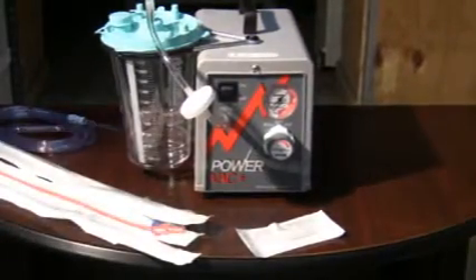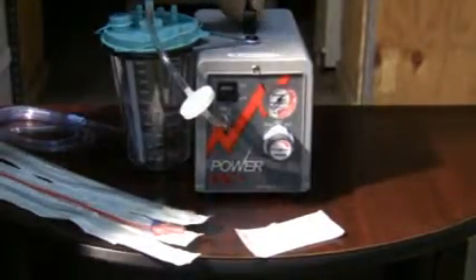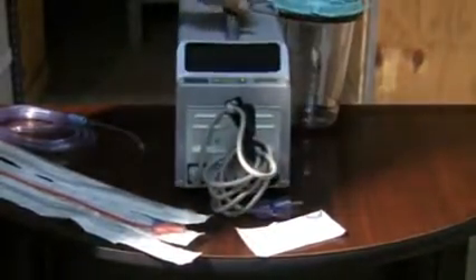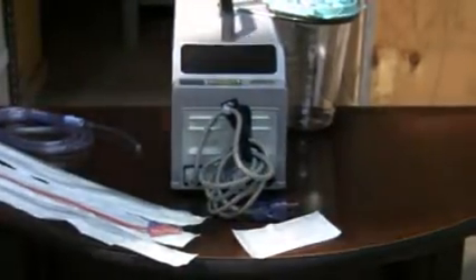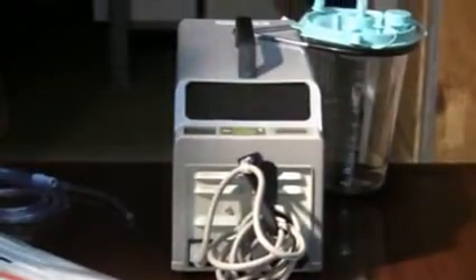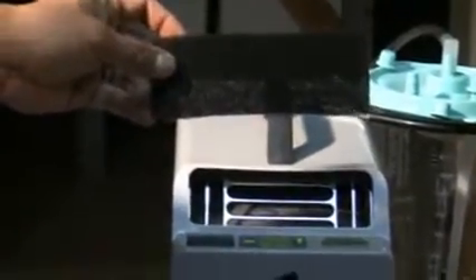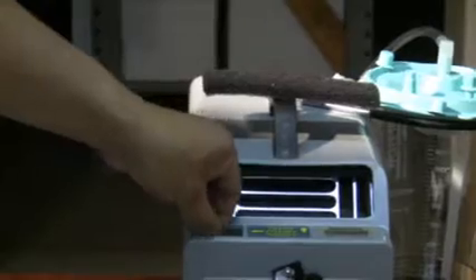When moving over to the back of your intermittent suction machine, you have two filters located on the rear side. Both of those filters should be cleaned weekly. Once a week for sure, twice a week recommended. Do not operate the suction machine when your filters are being cleaned. In order to clean your filters, you should remove them from the filter locations on the back side by simply pulling them out. Same with the other filter here.